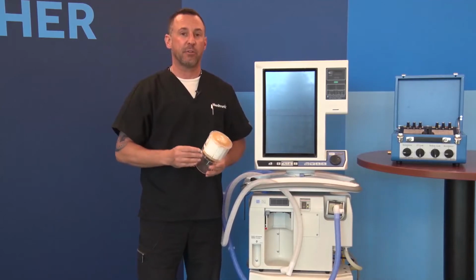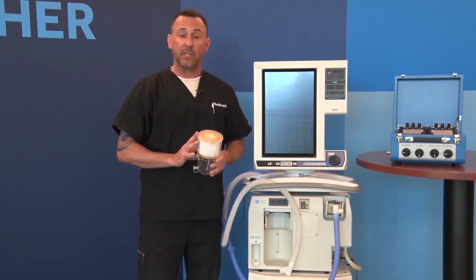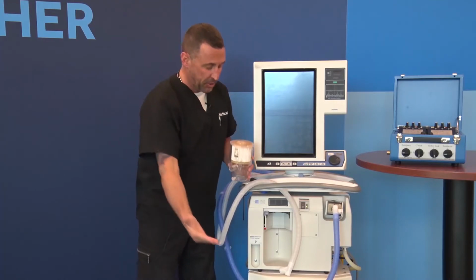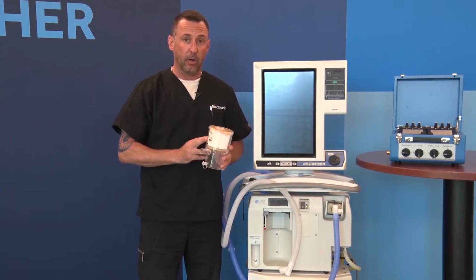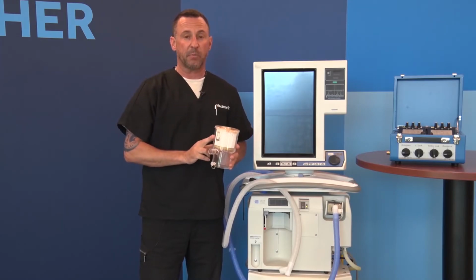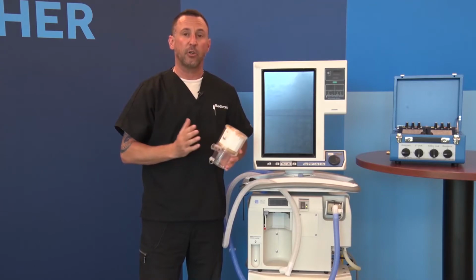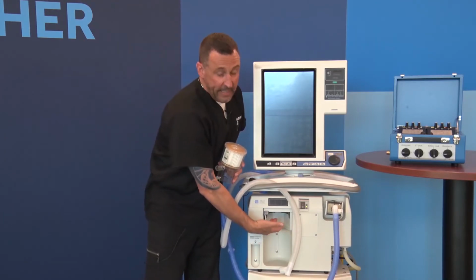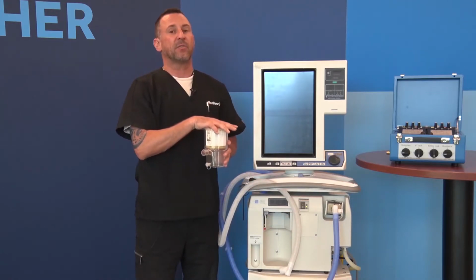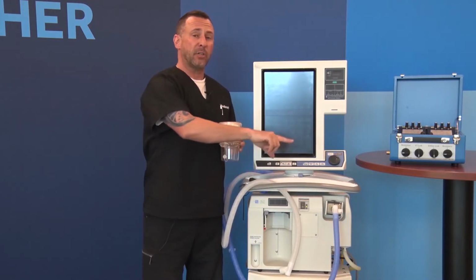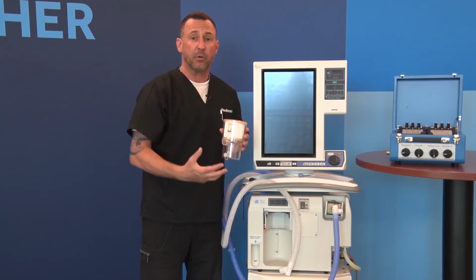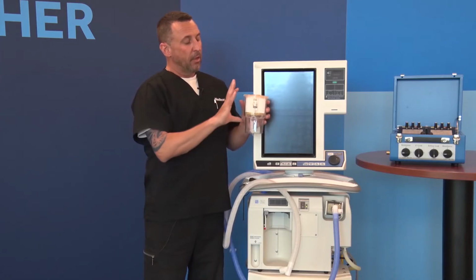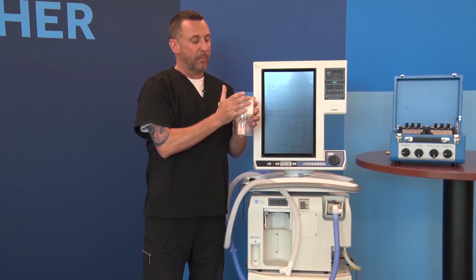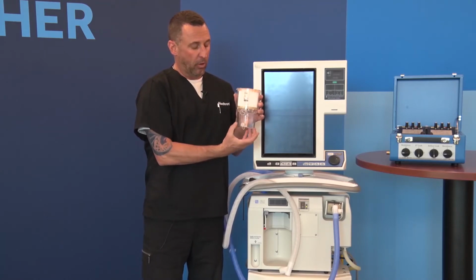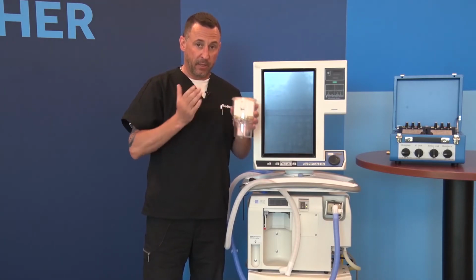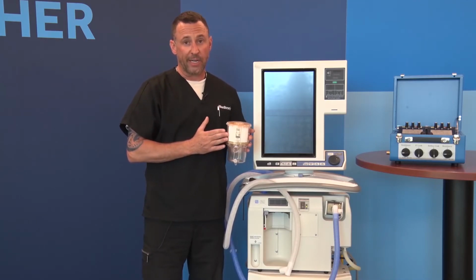Bigger number, better efficiency rating. An N100 rated filter means for the same 10,000 pathogens that the patient would exhale back to your ventilator, only three particles would escape this medium. So you have superior filtration in using a Puritan Bennett filter. There is a heating element inside the ventilator that actively heats this filter. That means any active humidification you're using, or say nebulizer particulates, things like that that can get into the circuit, they don't condense or rain out up here in the medium. They actually would rain out where gravity would take that water down at the bottom. So your filter medium, the important part of the filter, is not going to get occluded anytime soon.